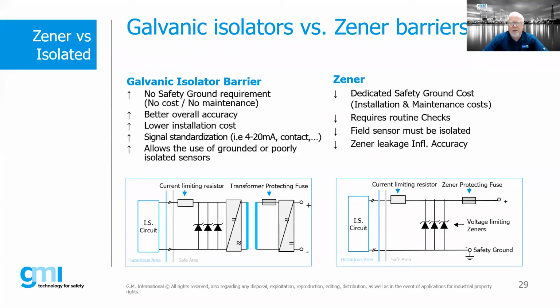Just to summarize a little, galvanically isolated versus Zener barriers: there is no safety ground requirement with galvanic isolation, better overall accuracy, lower installation cost. When you factor in the cost of the barrier but don't have to worry about earthing and grounding, installation cost can be less. Of course, Zener requires that dedicated safety ground.